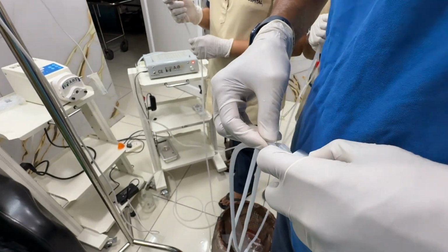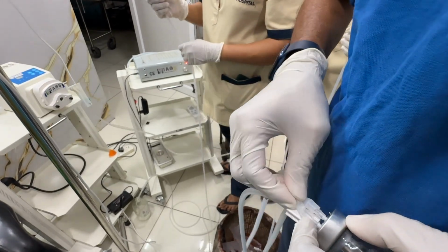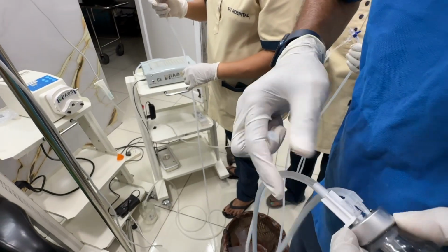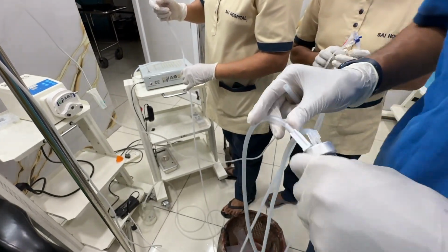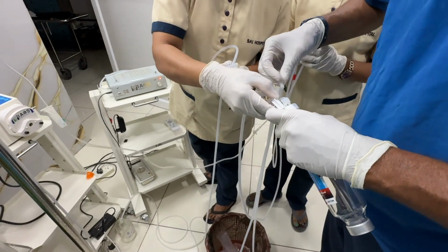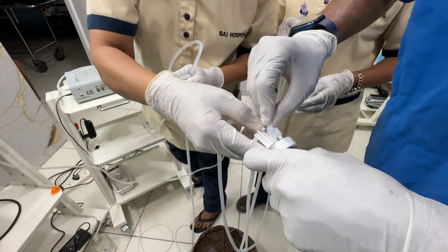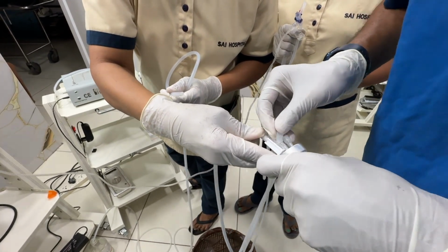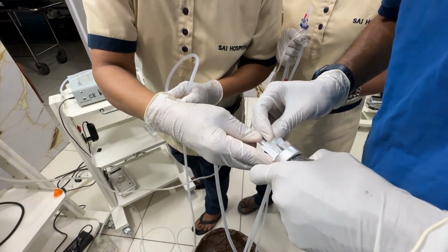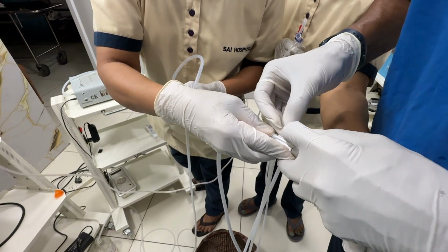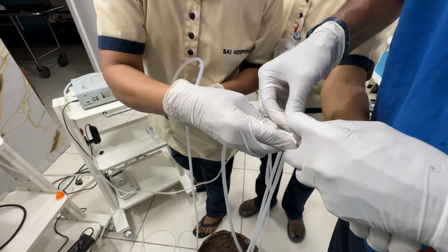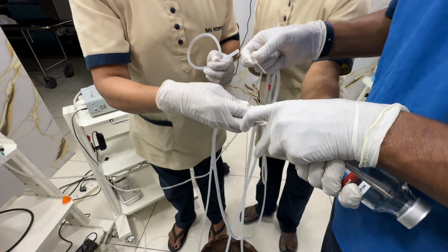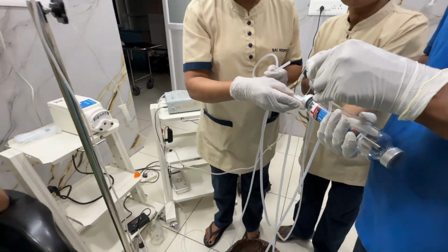Sometimes it may be extremely crowded and we may not be able to negotiate the tube into the needle. In such circumstances, it is better to remove the needle and push the tube in, or move the other connectors to the side to see that we have enough space to connect the needle into the ozone diffuser.